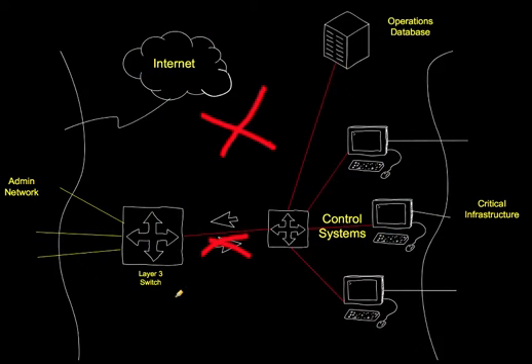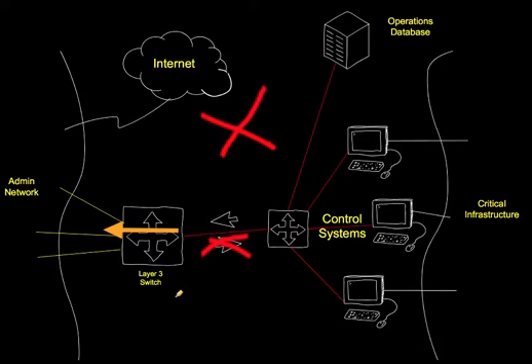All information created on the critical system VLAN is pushed to the appropriate admin or business management systems. The business management systems are not allowed to pull data from those systems. No traffic is allowed to pass from the admin network to the control system network.